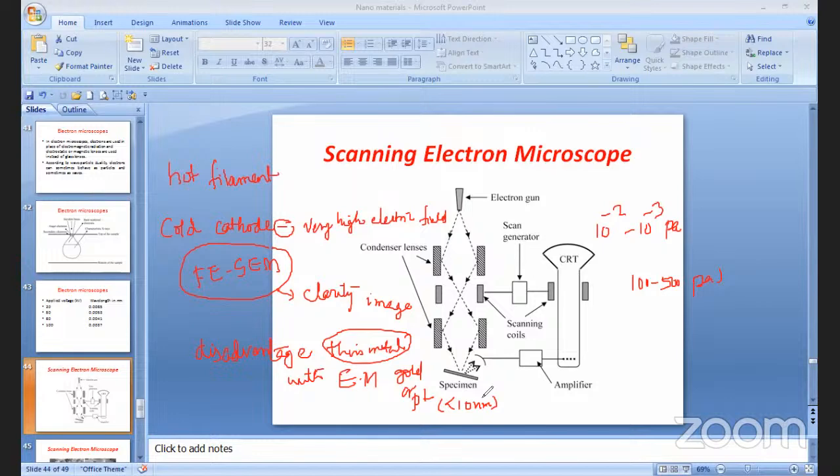Okay. So the metal film is usually sputter coated on the sample to be investigated prior to introduction into the electron microscope. This enables even biological samples to be analyzed using an electron microscope. Additionally, some of these microscopes provide a low energy electron flood gun to reduce the sample charging effect by providing more electrons to an insulating sample.